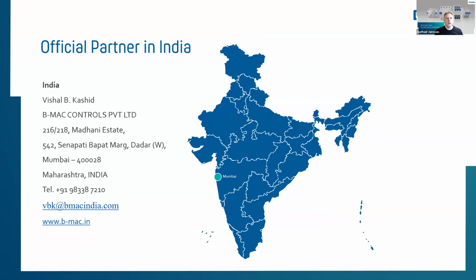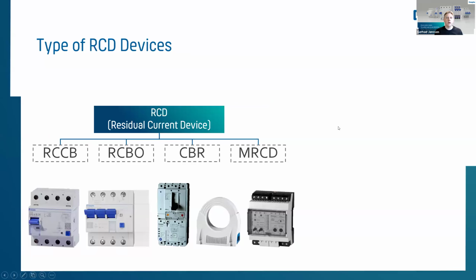Starting with the technique, the overall topic is RCDs, residual current devices, which are split up into different devices: RCCBs, residual current circuit breakers; RCBOs, residual current circuit breakers with overcurrent protection; CBRs, circuit breakers also with residual current protection; and MRCDs on the right side, which are monitoring devices, monitoring residual currents.